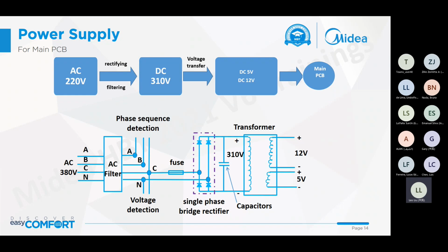Okay, for main PCB, the power supply is like this. First, we got the original three-phase power supply, 380 voltage. This voltage goes to the main PCB, which integrates a three-phase protector. So the power supply will be detected for phase sequence and also voltage. If the phase sequence is not normal or the voltage value is out of the range, an error code will be displayed.